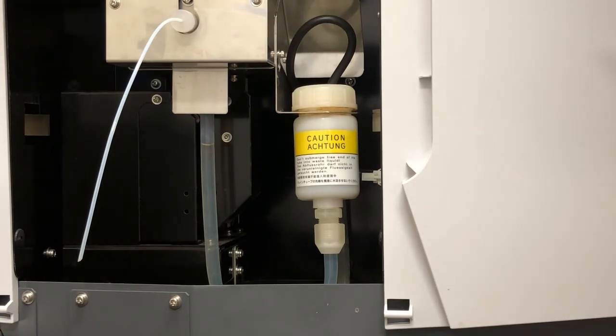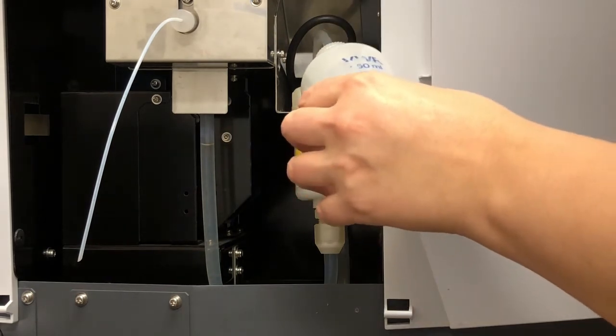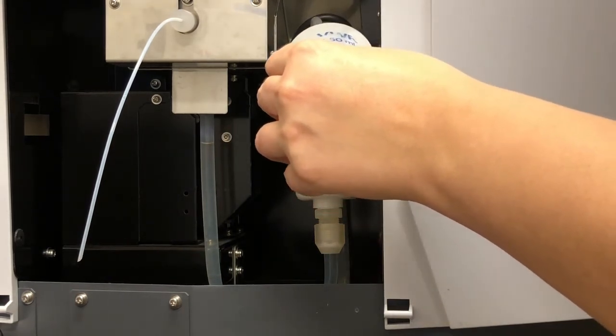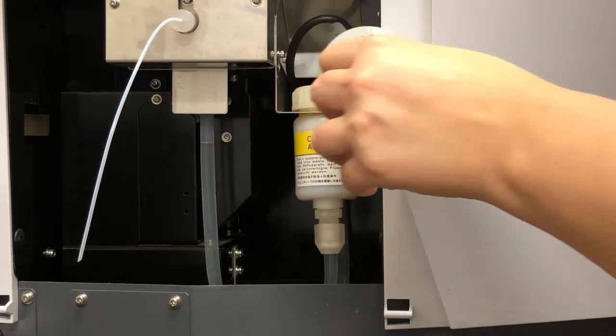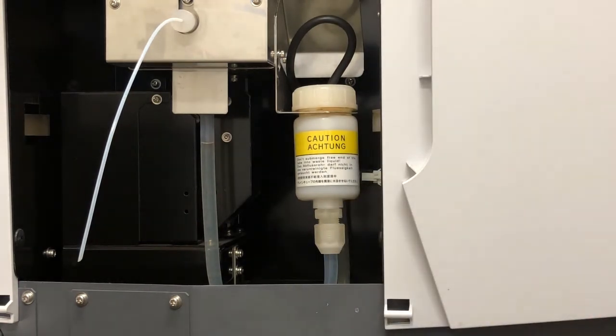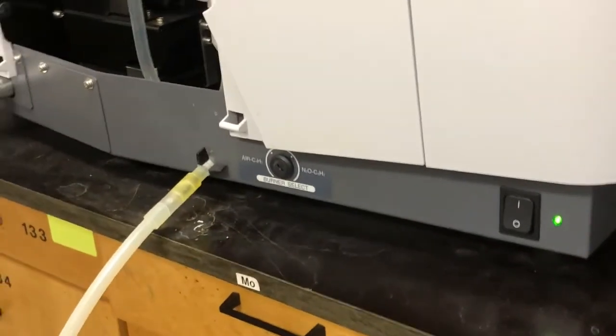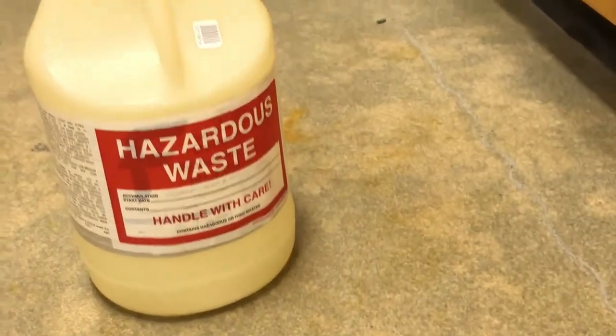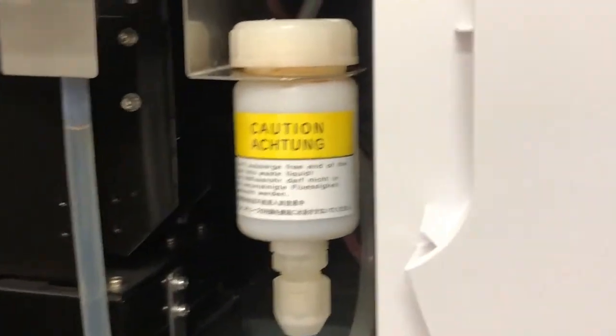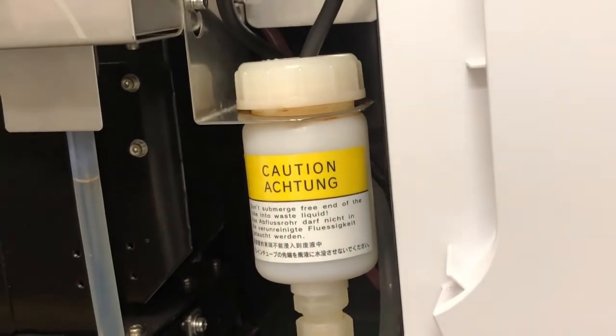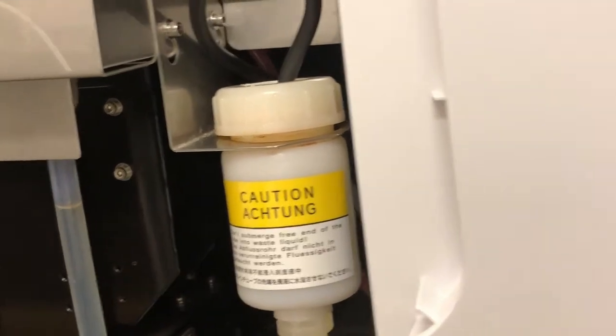The other thing that's important in this step is that this bottle is full of water. So we just fill it up with deionized water, and we can tell it's full because when it's full, we'll see some of the water pour out of the overflow here. Okay. Now, this drain sensor is also connected to a tube here that goes down to a hazardous waste bottle. That collects all of the waste that comes out of the machine. So excess solvent and anything else that comes out as waste, so it doesn't go into the environment and we can dispose of it properly. Okay, so that's the drain sensor.